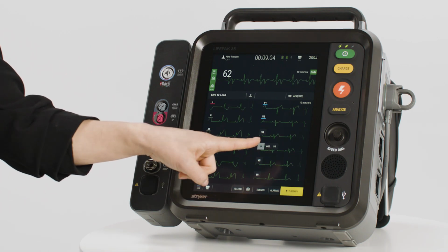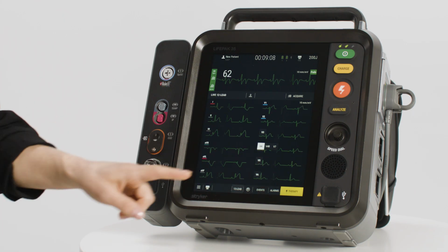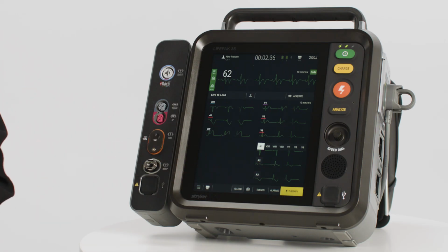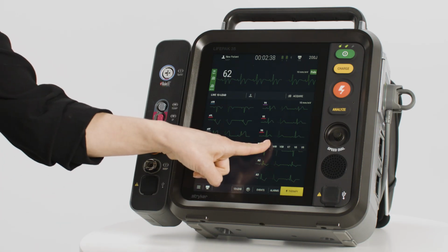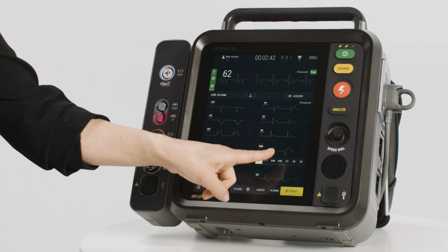When the 10-wire ECG cable is attached, leads V4 through V6 can be assigned alternate labels to reflect the actual wire locations. The alternate labels will appear on screen, in printed reports, and in transmitted reports. When the additional leads are used, A1 through A3 can also be assigned labels to reflect the wire location.